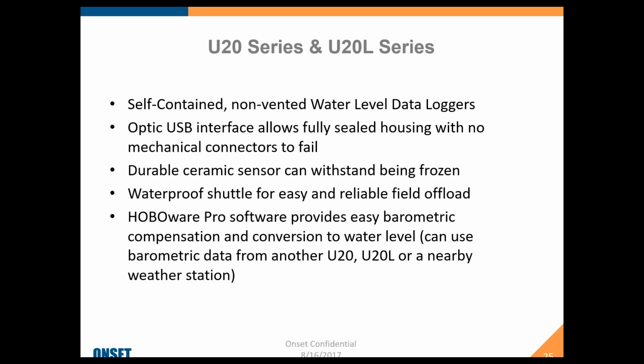It's factory replaceable, and the software tells you when the battery needs to be replaced. A question we get a lot is how cost effective it is to replace the battery, and it is worth your while. You can always call us to arrange that. It's about a $200 battery replacement, but we resend you a logger that's recalibrated with a new battery. So it's a great choice if you're deploying a logger and doing the barometric compensation in the software.